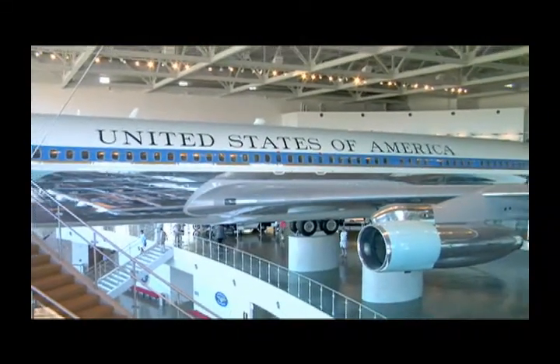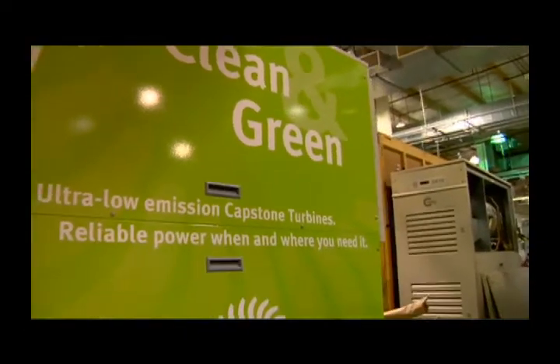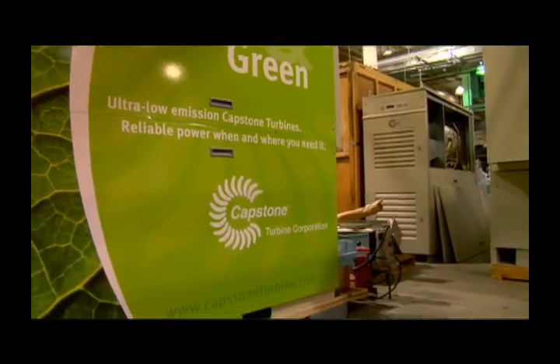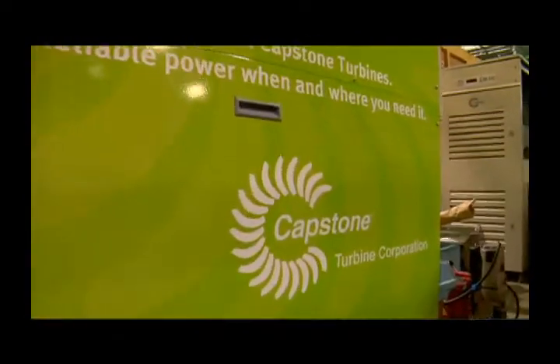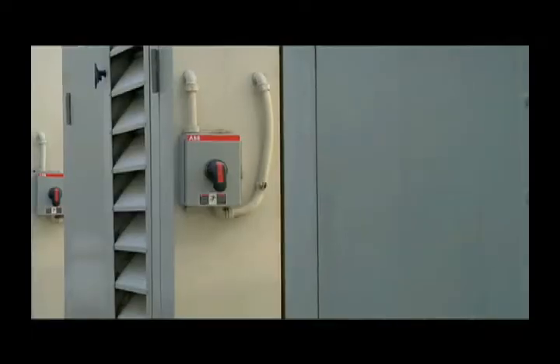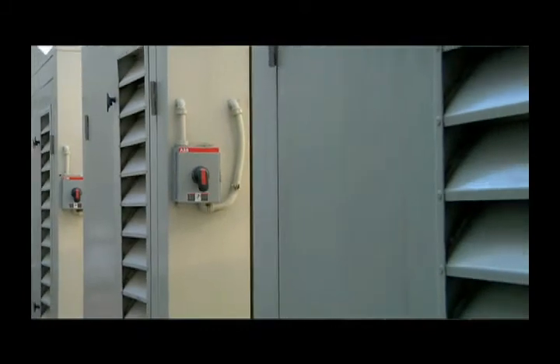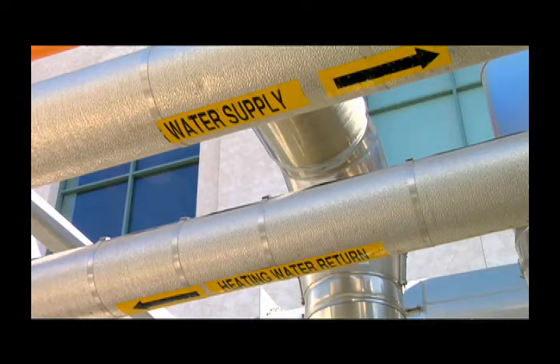A lot of people didn't know about this system when we first installed it, and there's a lot of people who still don't know about turbine systems. And we had some questions about the efficiency of the system, how well it was going to provide us our electricity, hot water and cold water out of one package. After 3 years of having this system installed, we've now learned that the system does give us the efficiency that we were looking for. It's a clean burning system. It does give us all the power for the entire campus. The chilled water capabilities and hot water capabilities are what we had anticipated from the manufacturers and from the engineers who put it in.